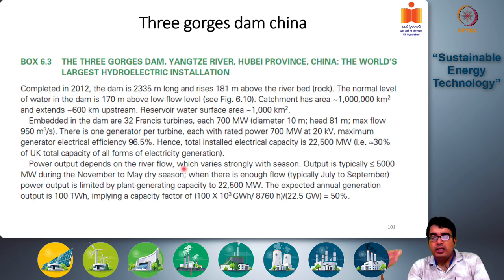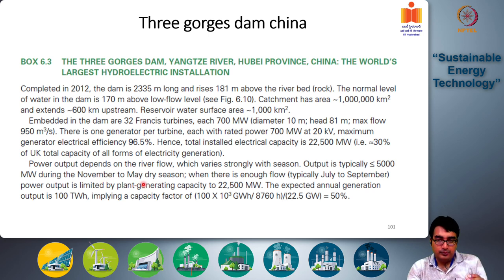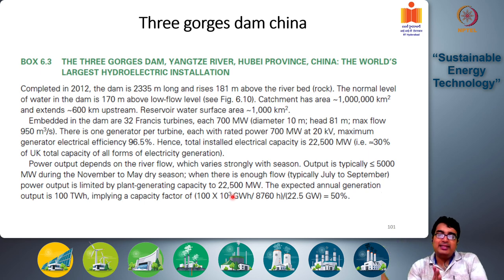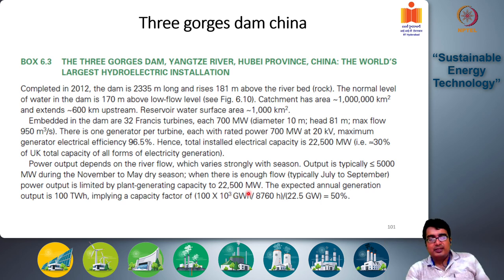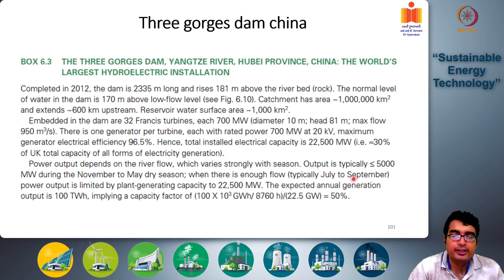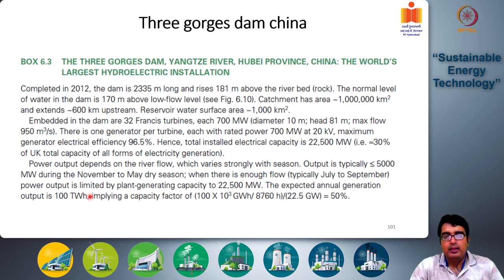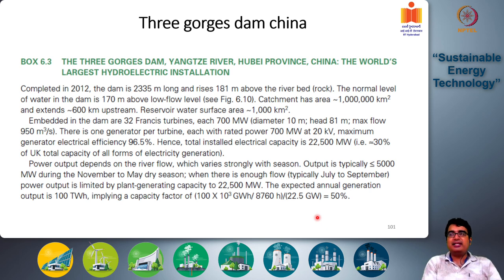One problem is that the river is highly seasonal. Output is typically less than 5,000 megawatts during the dry season from November to May, but during the wet season from July to September, the output can reach the full generating capacity of 22,500 megawatts. The expected annual generation is approximately 100 terawatt-hours, implying a capacity factor of around 50 percent.